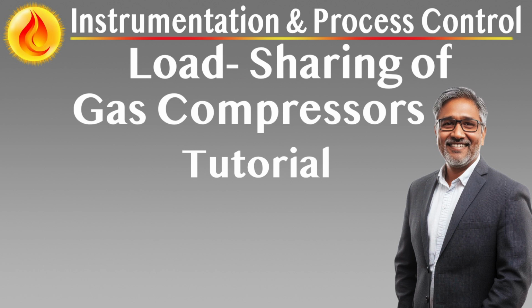Operational benefits. Uniform thermal loading reduces uneven heating across units, which can lead to differential expansion and stress. Reduced valve cycling minimizes unnecessary valve movement, prolonging actuator life. Improved control stability prevents oscillations caused by asynchronous recycle behavior. Process consistency maintains smoother transitions during load reductions or recoveries. Lower energy penalty. Balanced recycling prevents one machine from continuously blowing off, reducing wasted compression energy.